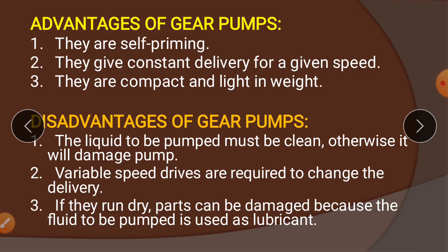Now let's see some disadvantages of gear pumps. The liquid to be pumped must be clean. Since the gears are meshing with each other, if the liquid has impurities such as rust particles or salt particles, it will lead to corrosion and wear problems. That will lead to improper working of a gear pump. So the liquid should be cleaned before it is fed into the gear pump. Otherwise, it will damage the pump.